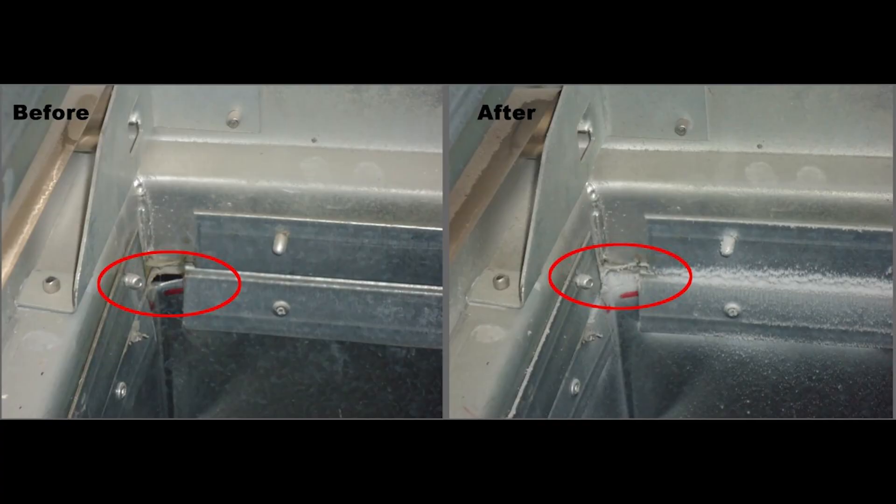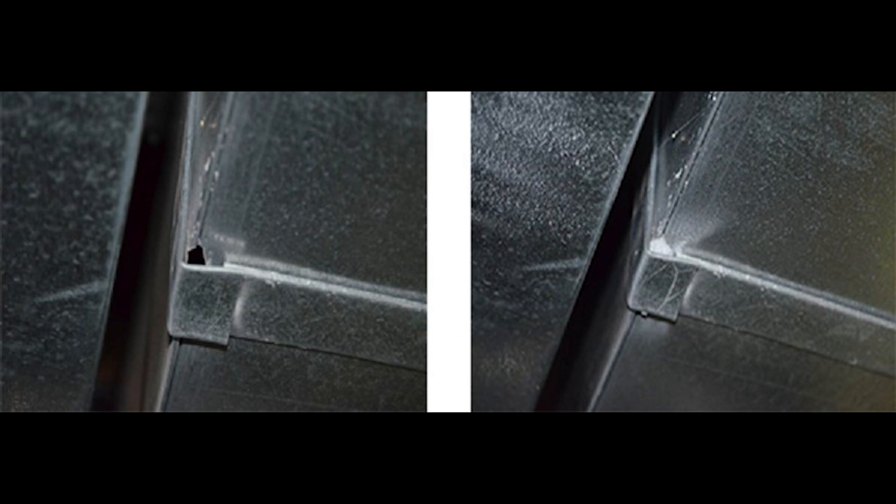The material will just be sealed in the ducts, captured in time. Before and after, the holes can be up to five-eighths of an inch in diameter and we can seal that up. Anything more than that would probably take too long to seal with this process, but that covers the vast majority of these holes. Additionally, this process is not just for elite giant commercial buildings — you could even do it at your own home.